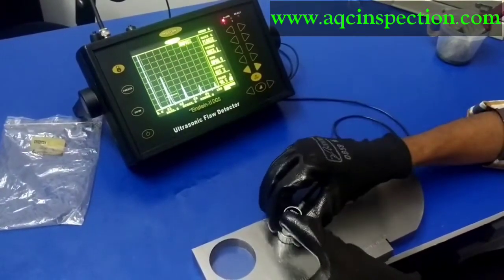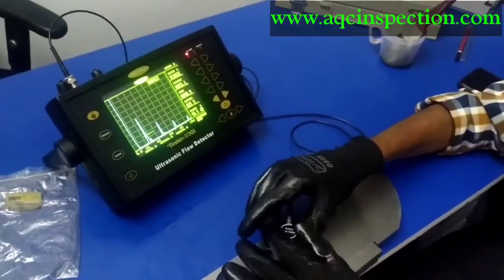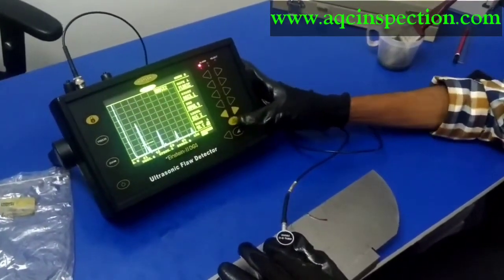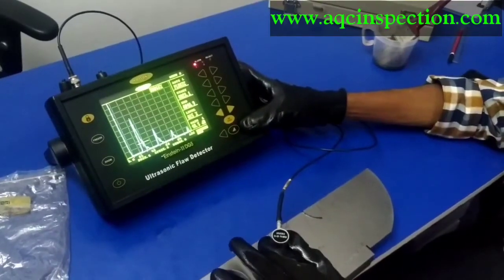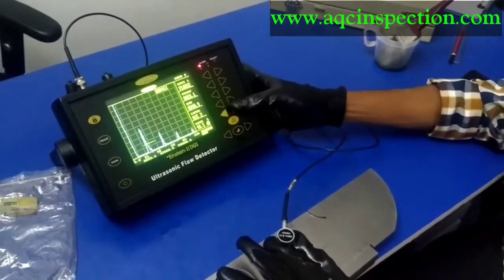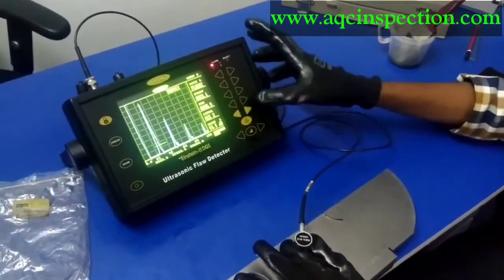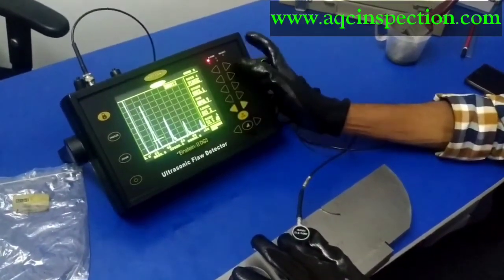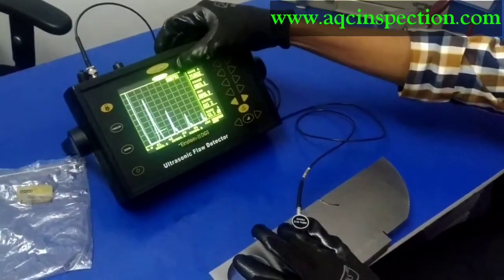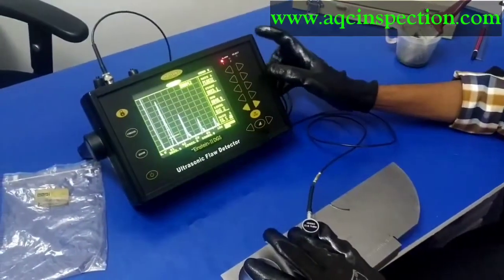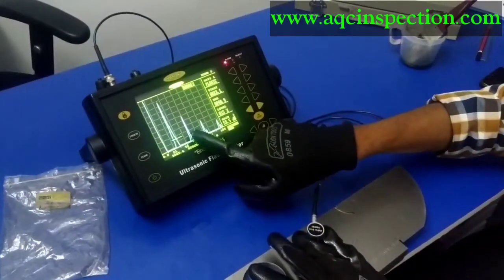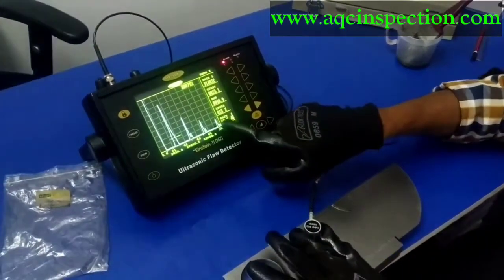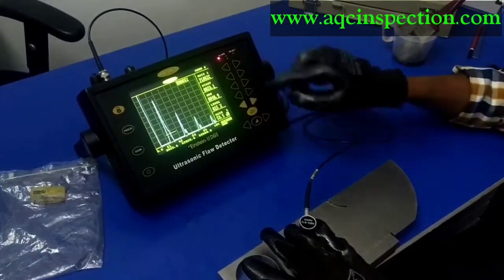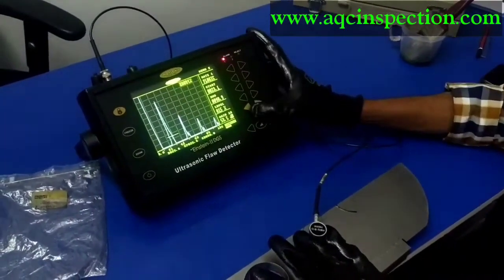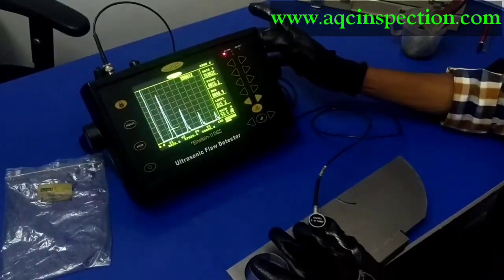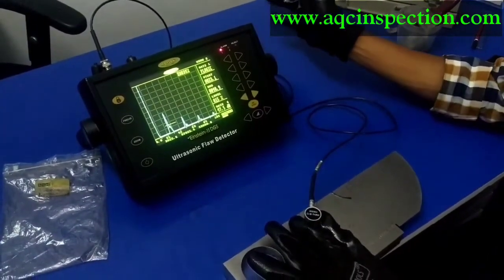Okay, right now I'm going to do the calibration for amplitude control linearity, which is for checking the gain. Right now I'm going to set the first backwall echo to 80% full screen height. As you can see here, you get the echo percentage right now. And the second backwall echo will be automatically set to 40, and this third one 20, and the last one as 10%. This is the dB step. I'm going to set 6 dB, as you can see, 6 dB, and decrease once we get 40% height.